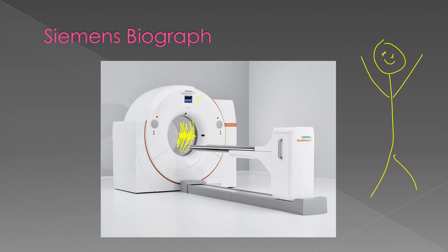And when you're actually scanning them, you have bed positions. So as you're planning your scan, it will look something like this. All the bed positions are the same. These are really your field of view, because you'll scan the patient in sections. And what that looks like is actually the different rows of detectors. So however many rows of detectors you have, that makes up one bed position. It's your field of view.